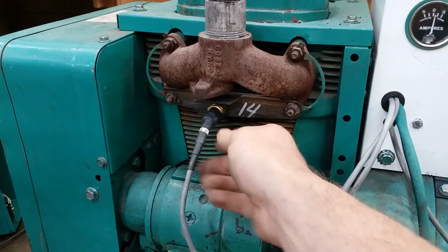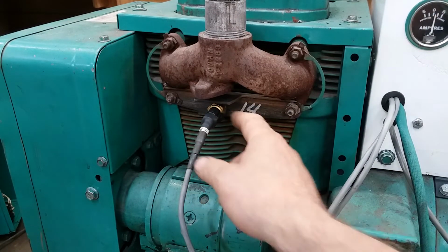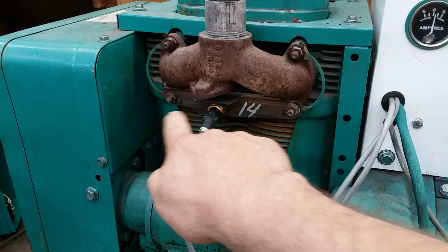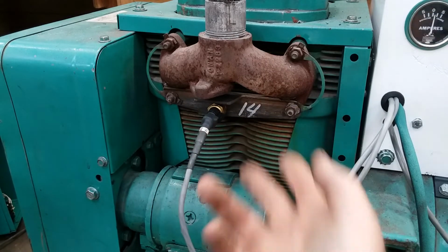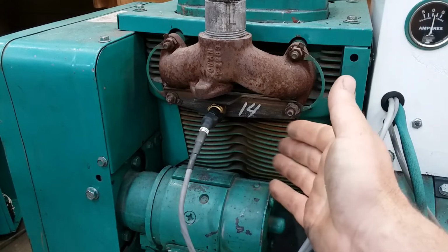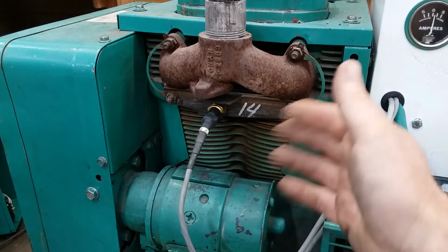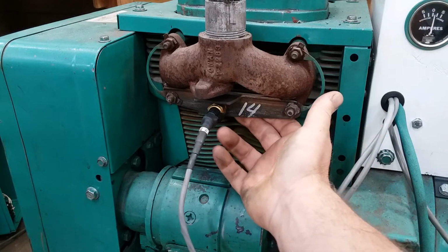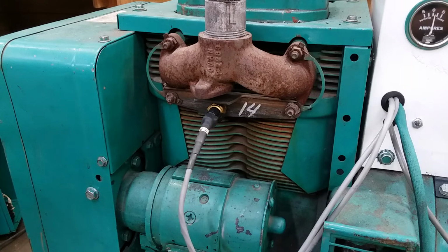And down here I've got another one of those same sensors, and I just built a bracket here to put this sensor in the cooling air stream as the cooling air is blowing out of here, to measure that cooling air temperature. And there are alarms that you can configure so that if your cooling air, or that other sensor, gets too hot, it shuts her down and trips it out.